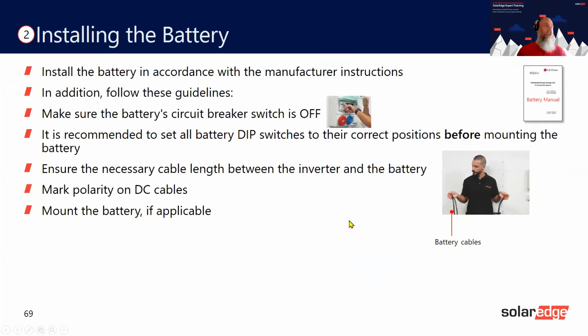Okay, we can skip this one. Apart from a very important one here: mark the polarity on the DC cables. Make sure when you get your plus cable that you mark plus on both ends. And then also make sure you've installed the dip switches correctly in the battery before. It's a lot easier when the battery's on the floor, as it's being delivered, you can set the dip switches. It makes it a lot easier.